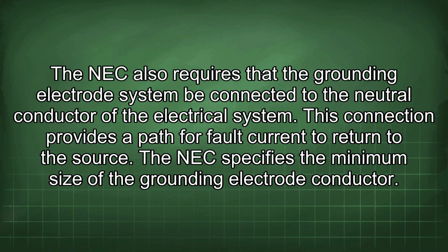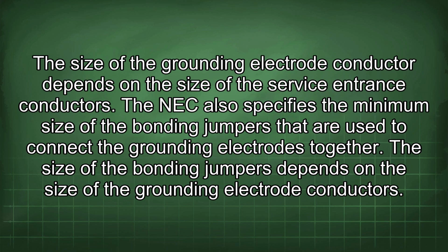The NEC specifies the minimum size of the grounding electrode conductor. The size of the grounding electrode conductor depends on the size of the service entrance conductors. The NEC also specifies the minimum size of the bonding jumpers that are used to connect the grounding electrodes together. The size of the bonding jumpers depends on the size of the grounding electrode conductors.